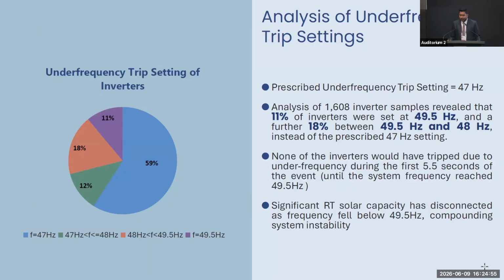Then at the same time, we analyzed the under frequency trip setting of the inverter samples which were collected. Even though the under frequency trip setting was prescribed at 47 Hz, it was revealed that 11% of the inverters were set at 49.5 Hz, and a further 18% between 49.5 Hz and 48 Hz instead of this prescribed 47 Hz limit. Therefore, it could be determined that none of the inverters would have tripped due to under frequency during the first 5.5 seconds of the failure, until the system frequency reaches 49.5 Hz.